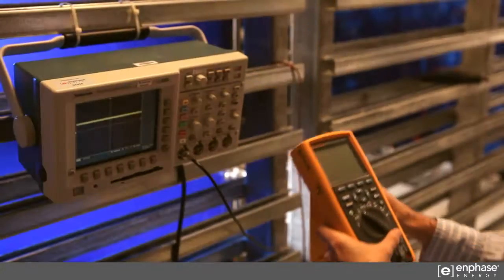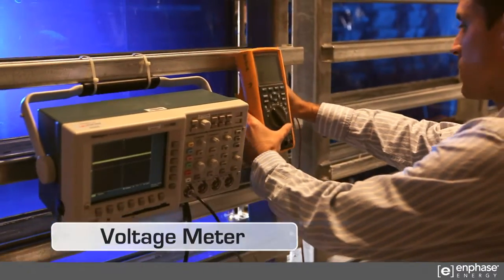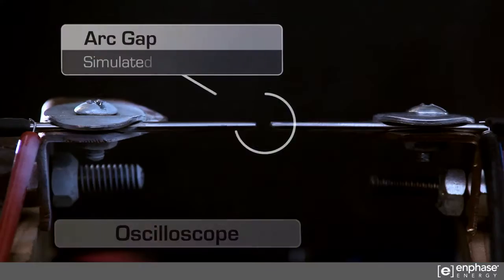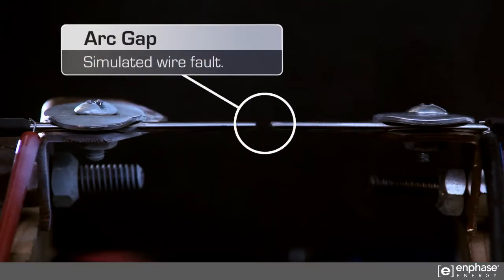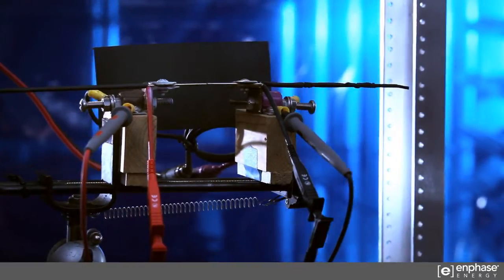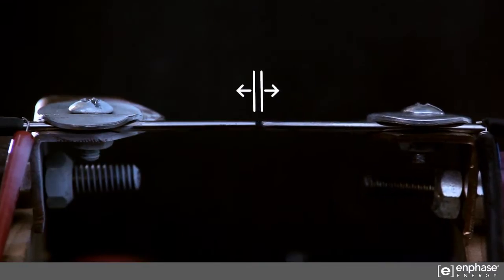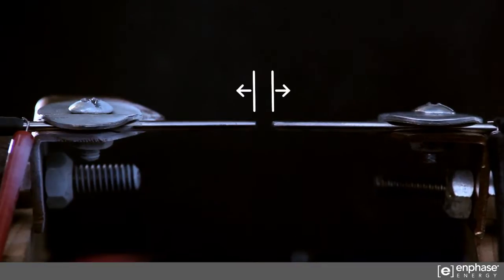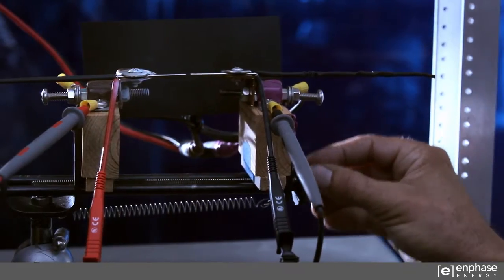In this demonstration, we have a meter, a scope, and a gap to simulate a wiring fault. The experiment will begin with no gap. The rods will then be slowly pulled apart, simulating an arc gap from a wiring fault, such as a loose connection.